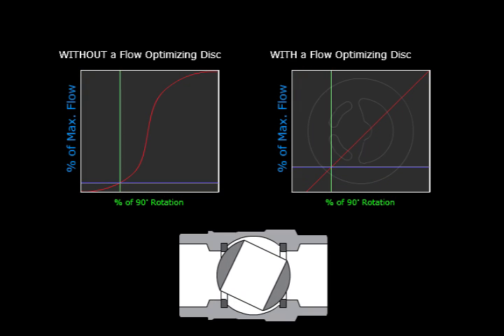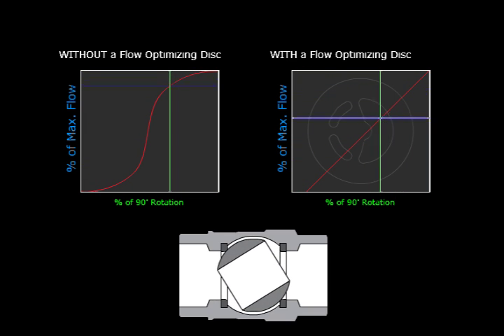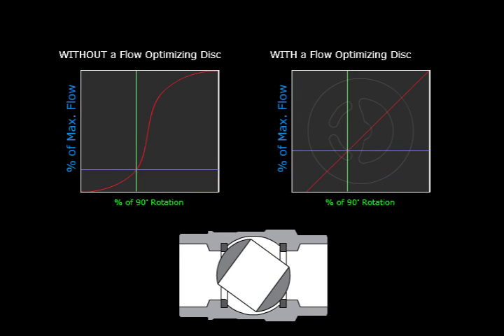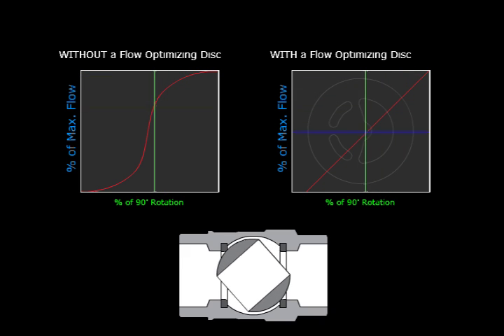The purpose of the flow optimizer is to make the flow rate increase evenly in direct proportion to the rotation of the ball. These curves clearly illustrate the principle. See how the percentage of flow on the valve with the optimizer disc increases at a steady slope as the ball rotates?